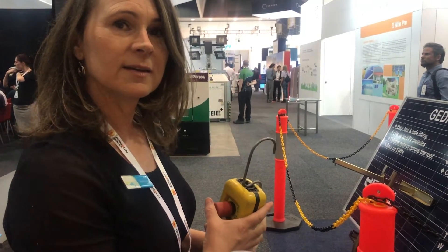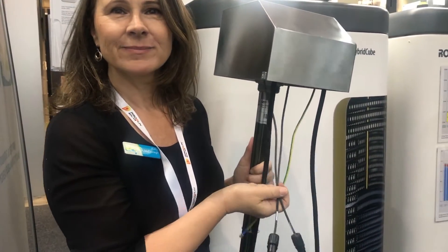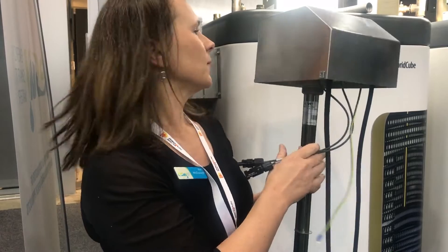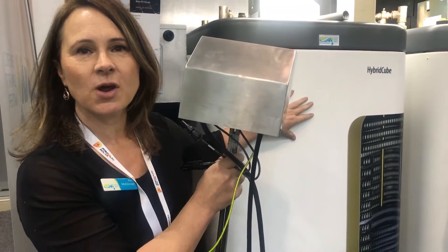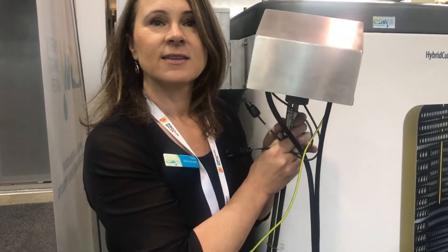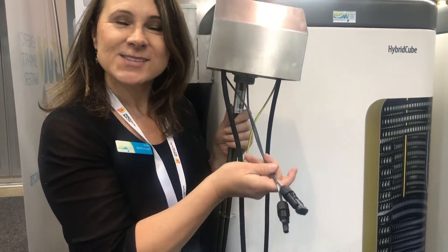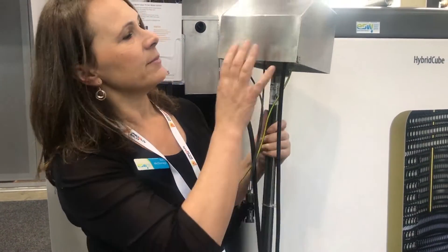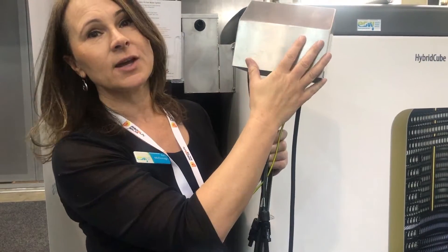Let's have a look at what else you've got on the stand. So Kelly, what's the strange thing you're holding in your hand? So this is our solar PV water heater. This particular device has been designed in Austria. It has a 2 kilowatt DC element and a boost AC 2 kilowatt AC element as well. It's designed to heat the water in this unpressurised Rotex heat exchange tank. It requires a 2 kilowatt dedicated PV array off-grid, so no grid connection required for that array. It has an MPP tracker within this enclosure, and it heats the water inside the tank to up to 85 degrees Celsius.